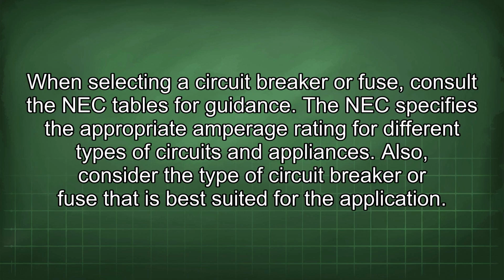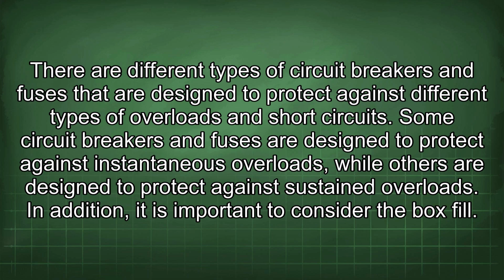When selecting a circuit breaker or fuse, consult the NEC tables for guidance. The NEC specifies the appropriate amperage rating for different types of circuits and appliances. Also, consider the type of circuit breaker or fuse that is best suited for the application. There are different types of circuit breakers and fuses that are designed to protect against different types of overloads and short circuits. Some circuit breakers and fuses are designed to protect against instantaneous overloads, while others are designed to protect against sustained overloads. In addition, it is important to consider the box fill.